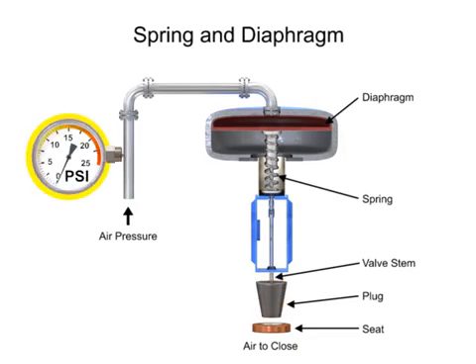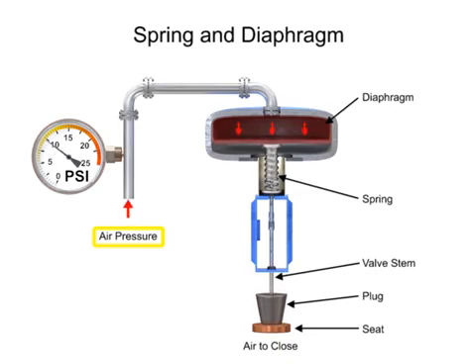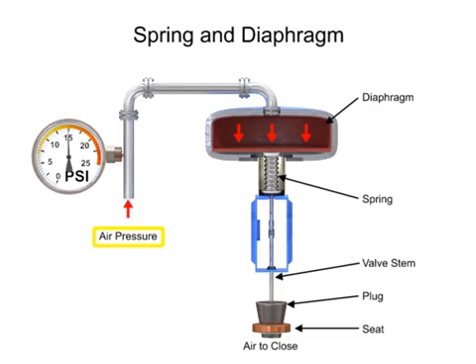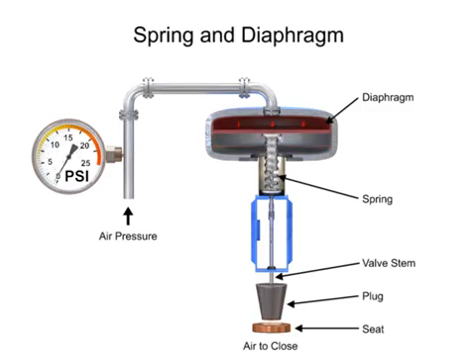A 15 PSI pneumatic signal enters the housing at the top of the actuator. As pressure is exerted on the diaphragm, a downward force is applied against the spring which moves the restrictor. The diaphragm moves until it creates an equal but opposing force against the spring, at which time the motion stops as the plug meets the valve seat. With no air pressure, the restrictor is pushed upward by the spring to act as a normally open control valve.